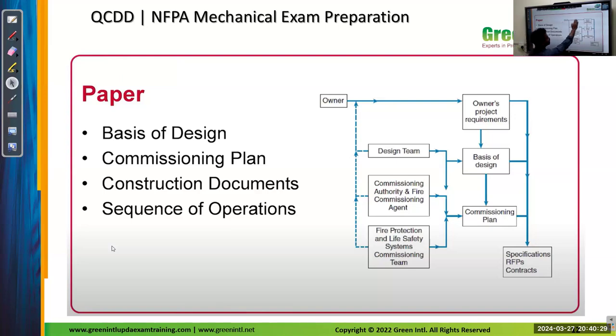The owner gives the project requirements. Based on the project requirements, they will prepare a design. And based on that, the design team will give the proper design. Once the design is finished, they will go to the commissioning plan. So the commissioning plan will have the specification contracts, and the fire commissioning agent and the fire protection and life safety team will work together on the commissioning plan. Once it's done, they will provide the specification contracts. So it will show whether the owner's project requirements are met or not.